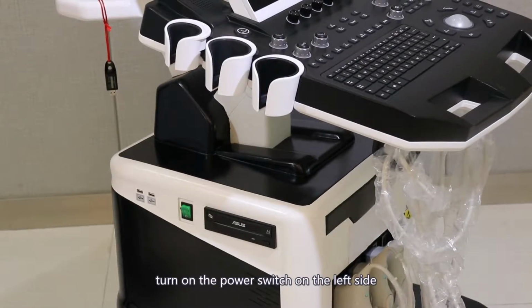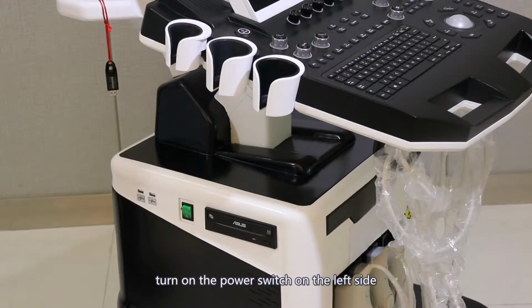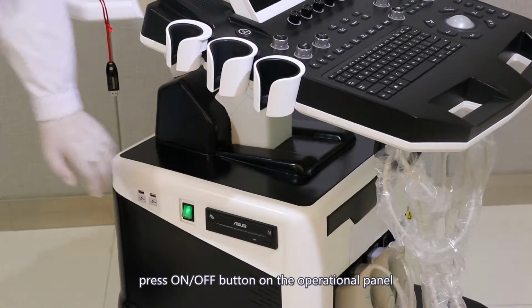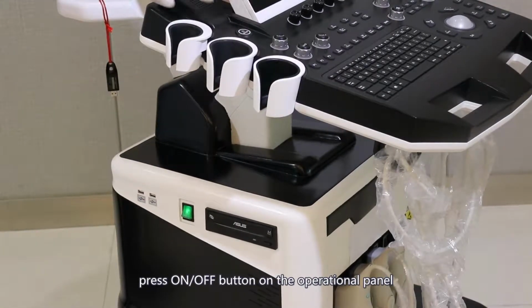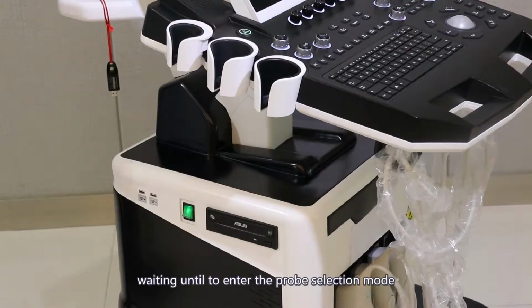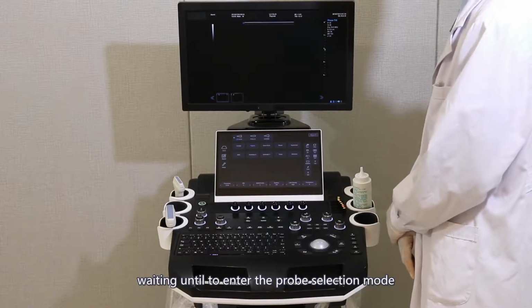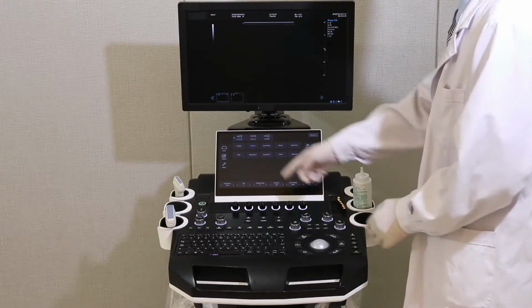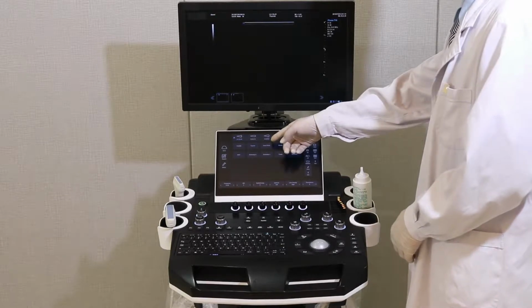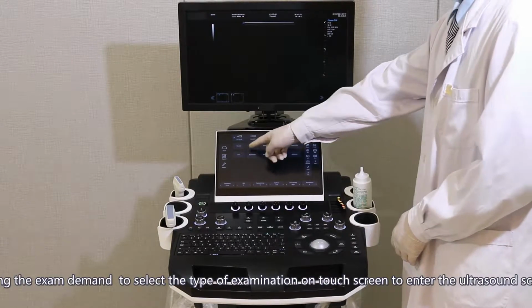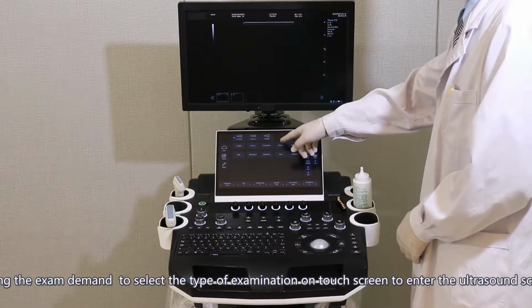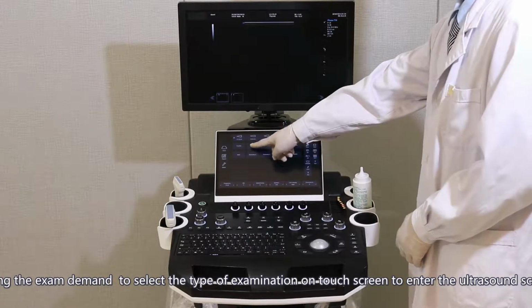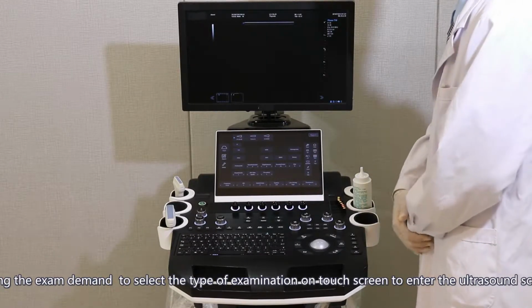Turn on the power switch on the left side. Press on or off button on the operational panel. Waiting until enter the probe selection mode. According to the exam demand, select the type of examination on touchscreen to enter the ultrasound scan state.